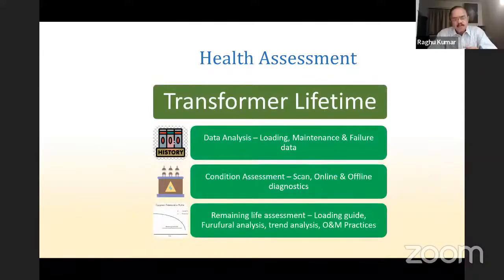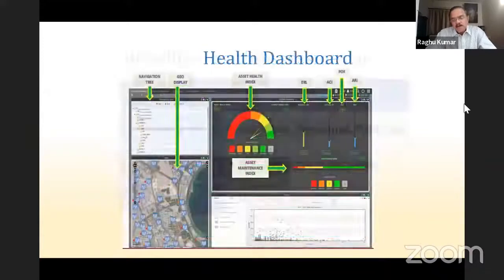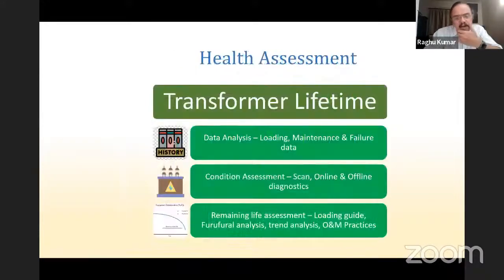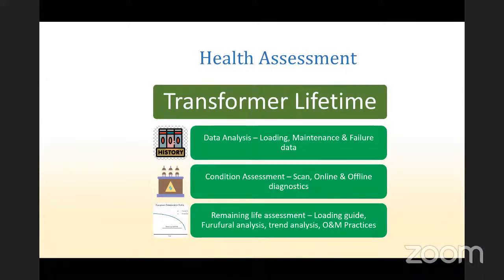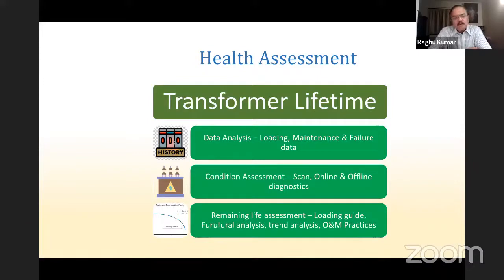Transformer lifetime calculation. Data analysis is from the historical records of loading, maintenance data, and failure data, all taken from the historical data. Then condition assessment data is for the present status. The present status is taken from scanning, online and offline diagnostics. All this information is taken from the condition data. And the remaining life assessment is carried out by the loading guide, which is available in IEC standards, and also furfural analysis. This gives you the quality of the paper. The DP value of the paper in a good transformer will be over 1000. And if it falls below 200, the transformer is about to fail any time. Then certain trend analysis and O&M practices give you the remaining life calculation.